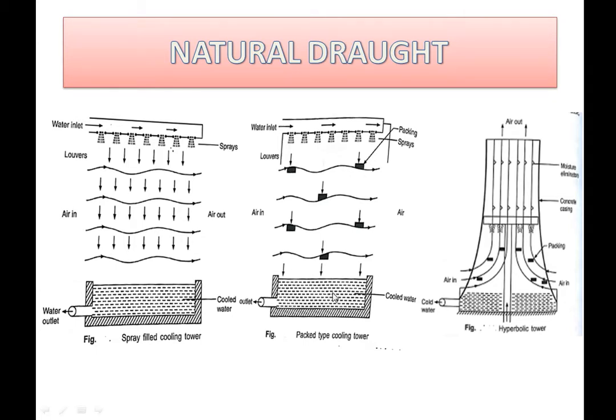The second one is the pack type cooling tower. You can see that it is same as that of the spray filled cooling tower but it has some difference as there are packing sprays which increase the wetted surface area of the water and break the water into smaller particles. These packing sprays will increase the evaporation process and thus the efficiency of the cooling system.